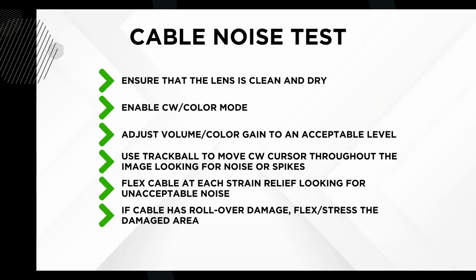So in this particular system, again, we're on the same exam, carotid here. I would go into the color mode and bring up the color box. If there was a flat area on the transducer where it had been run over, or nicks or damage in the cable, I would go to that area and give it a flex. Check to see if I see any spikes or noise within this color box right here. Sometimes you can increase the gain of that color. I'll show you what it looks like when it's all the way up. So this is color at 100%.